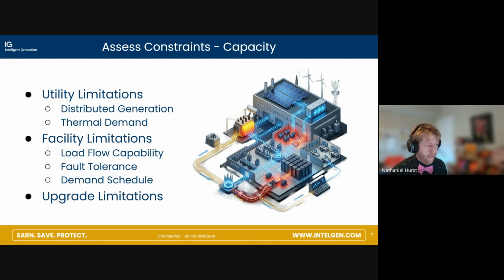Another thing I want to point out here is one of the many boogeymen of these projects: fault tolerance. Inverters, batteries, solar, they store a good amount of charge, and every electrical system you work on has an interruption capability. It's very important that the extra devices you add don't exceed that interruption capability, or fault tolerance, or you'll end up upgrading everything.